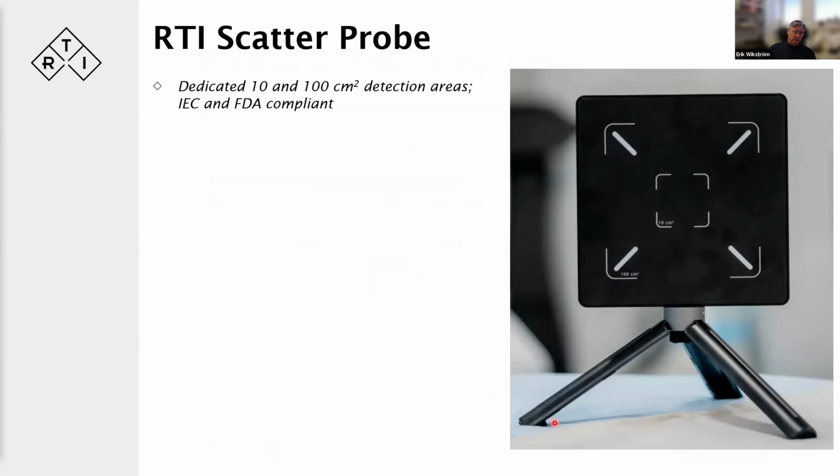We've got a 10 square centimeter area for some of the steady state applications, and we have a 100 square centimeter area right here for most of the leakage radiation, and also for the scatter radiation. So it's compliant with both IEC and FDA.